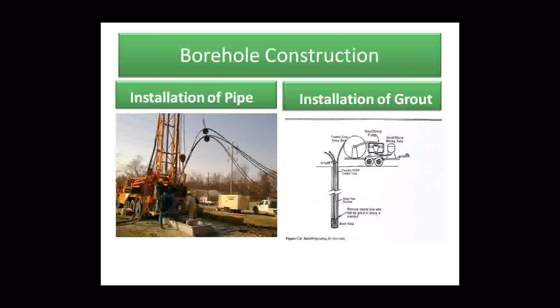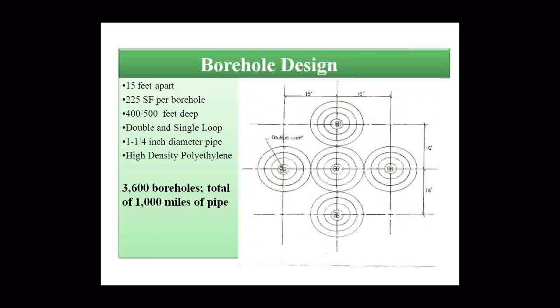What's key about the borehole design is ensuring that you have the correct spacing so that your thermal energy flow doesn't have a detrimental effect from one borehole to the next, which is a study that we want to undertake here using our geology department staff and the graduate students. But the point to make here is that 3,600 boreholes is about 1,000 miles of high-density polyethylene pipe that's inserted in the ground to get that total capacity we need for our campus.